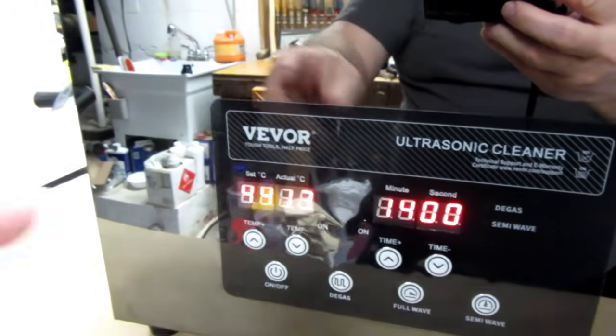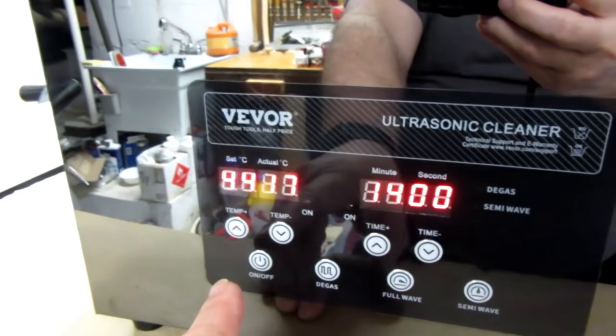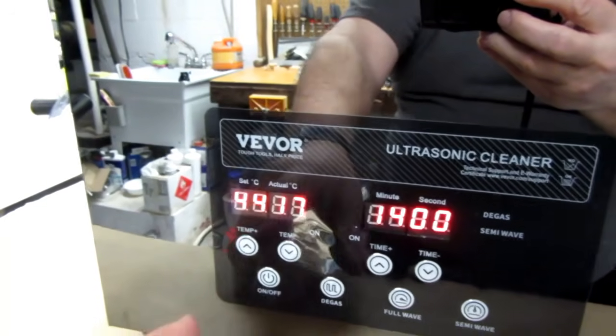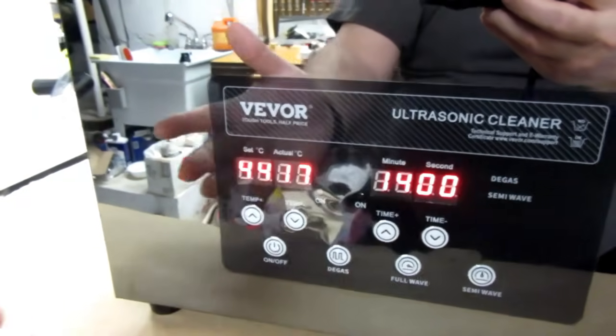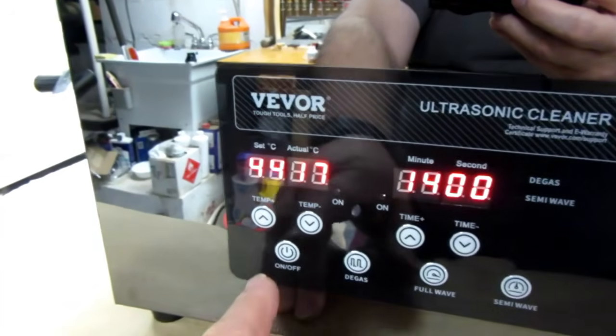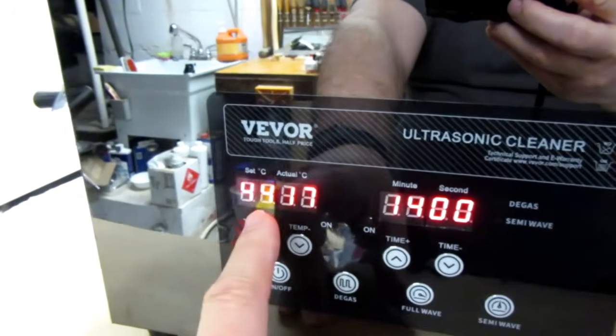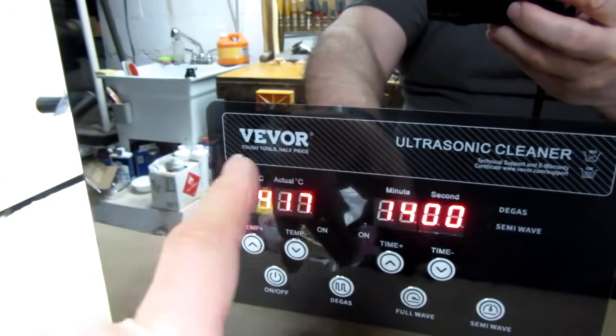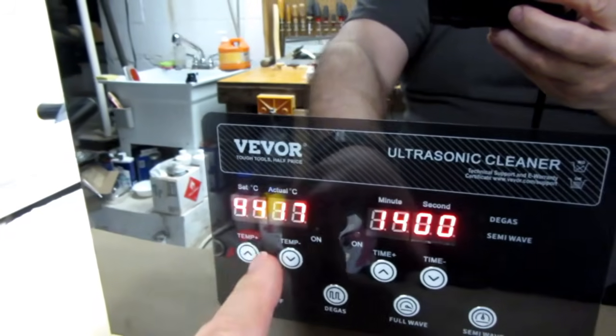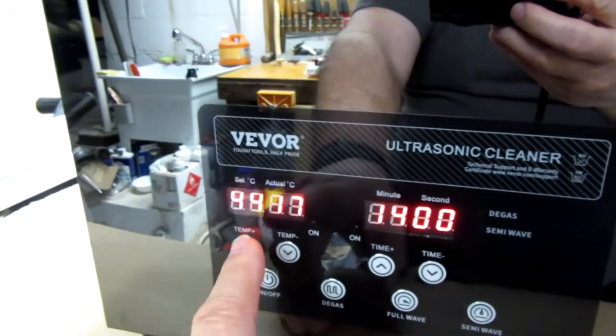Industrial units can do better, but these commercial ones for home and light industrial use don't have much to cool the transducers besides an internal cooling fan. More expensive units have better cooling. You don't want them to overheat, and the manuals say don't run continuously more than an hour, for example, which seems to be boilerplate on the Vevor manuals. They say 1 hour maximum, then let it rest to cool down.